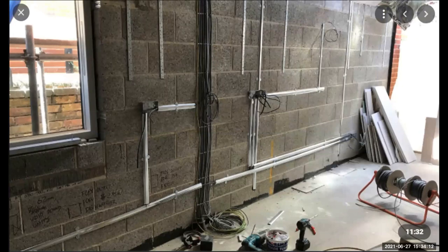Personally, I wouldn't use this as an excuse to do this, but that's just my opinion, and it's not my job. But I'm going to use this picture to highlight how someone could interpret the regulations incorrectly and, in fact, put electrically unskilled people at risk. Because once this is plastered, no one is going to know where these cable runs exist.